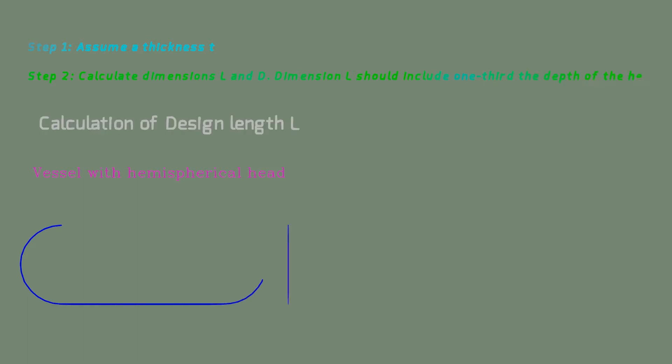In step one, we assume a thickness T — any value such as 5, 10, 15, or 20 mm can be assumed at the start. In the next step, we calculate dimensions L and D, where L is the design length and D is the inside diameter. The dimension L should include one-third the depth of the heads, which is important for all vessel types.